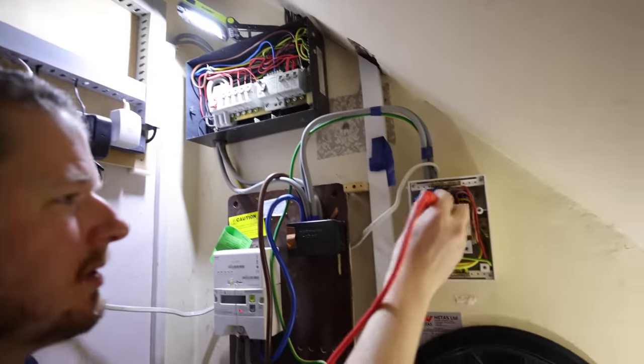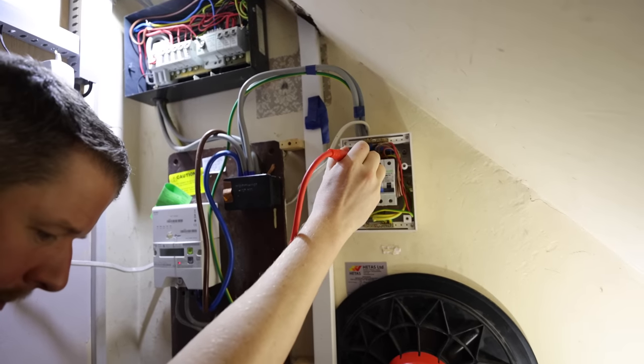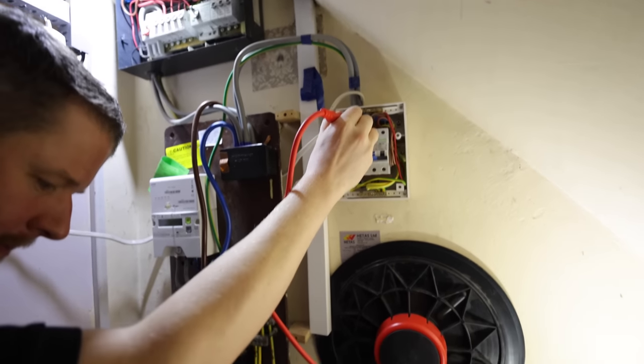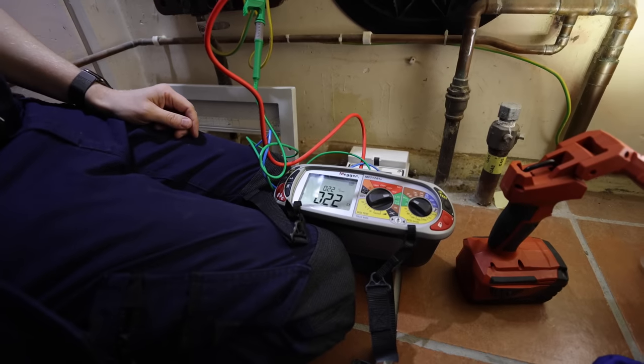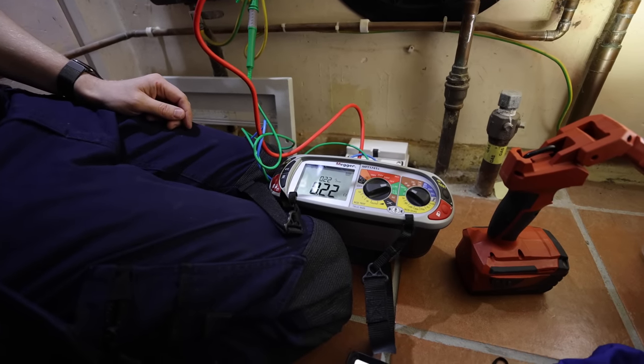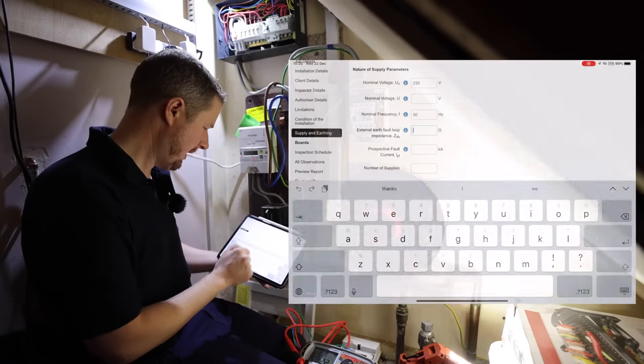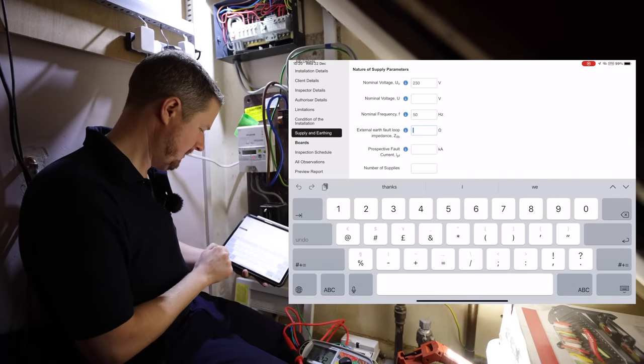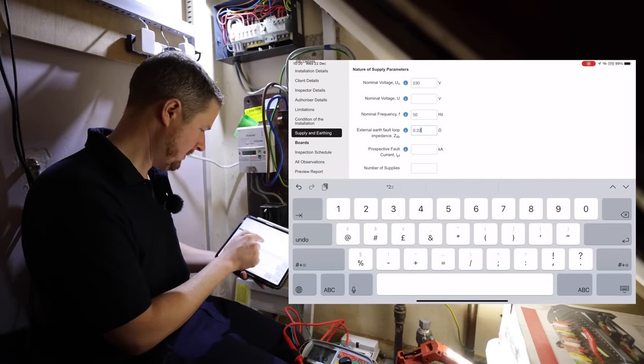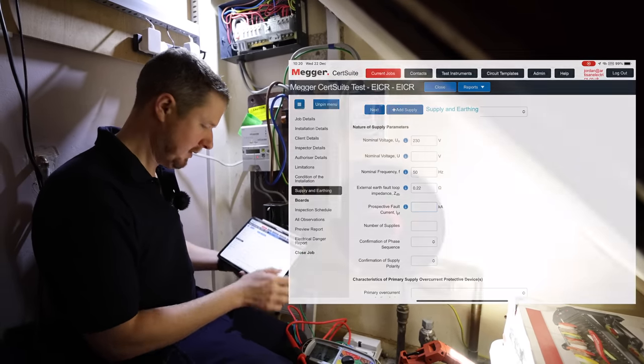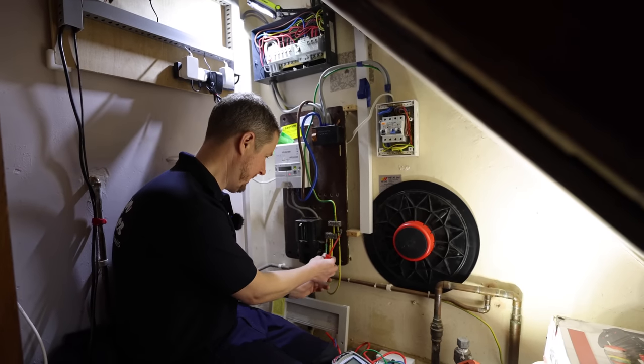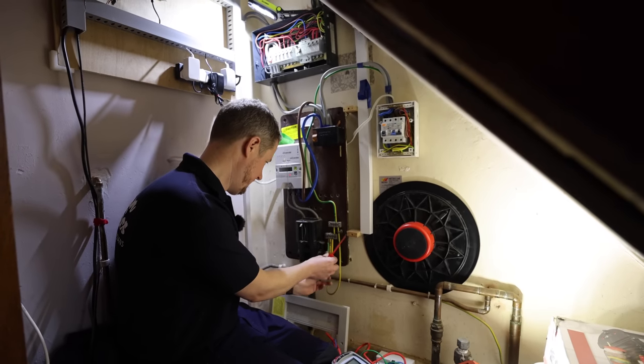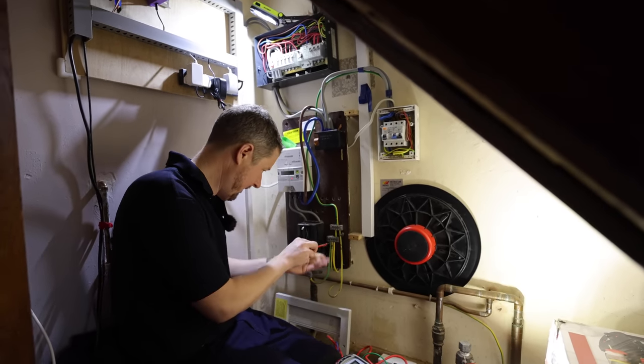We clip one crocodile clip on there, and then the other one on the incoming live conductor, which I'll just do on this board because it's easy. So we've got 0.22, absolutely fine. So we'll put that in, our Ze 0.22.